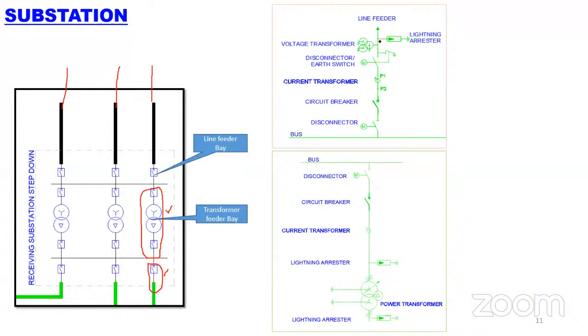Number 1, there is a switching surge. When you connect the load or when you switch on the breakers, let's give a layman's explanation. In our home, if you try to switch on your normal light switches, you can see there is a spark in it, which is generated by some surges. Like that, in extra high voltage and high voltage networks, there will be surges when you close the switches. So when doing this operation, there will be a surge.